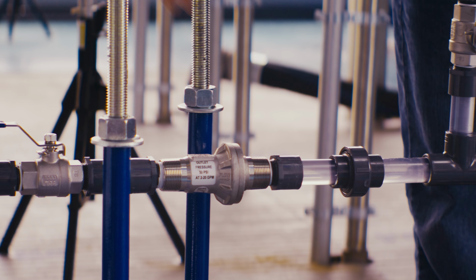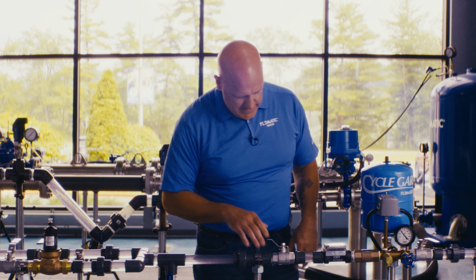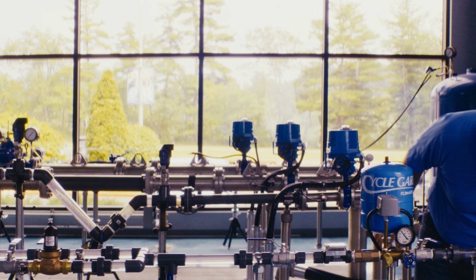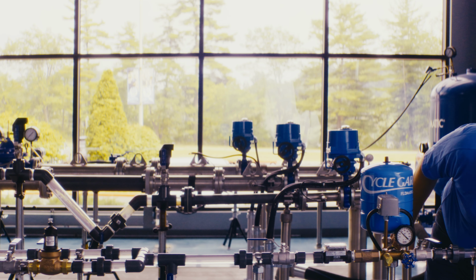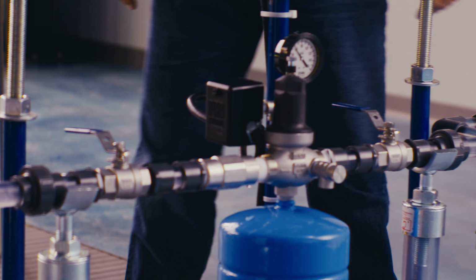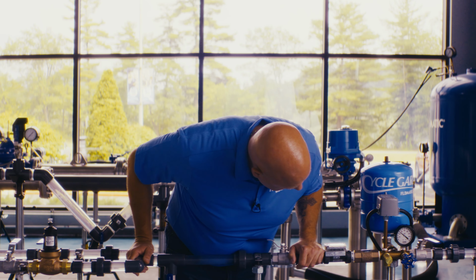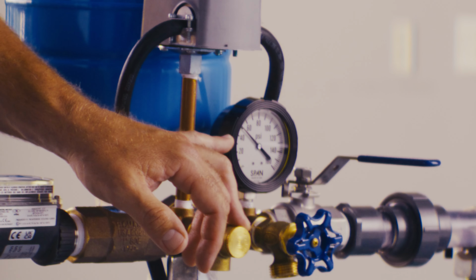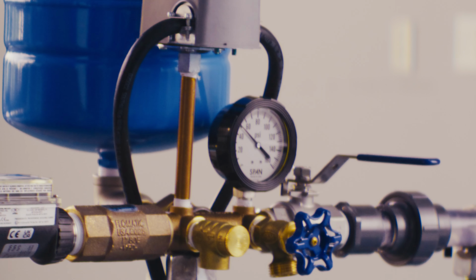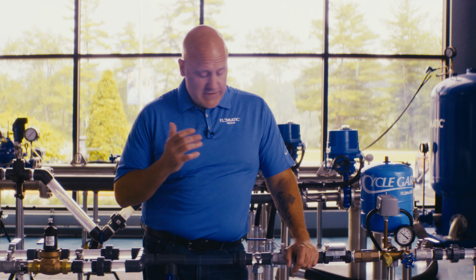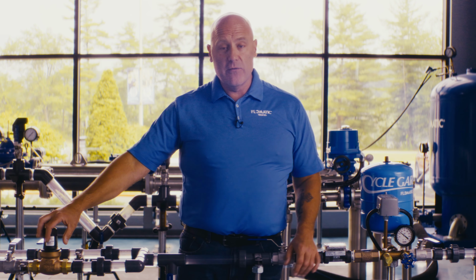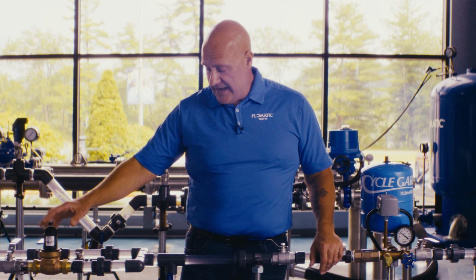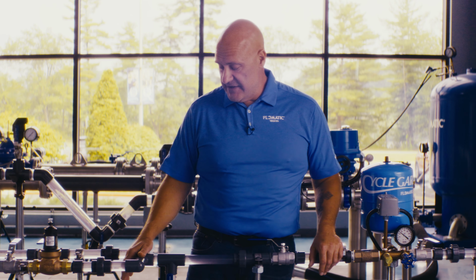So let me make sure I have the correct valves open. I do, and we will run it again. So our pump just kicked on, and you'll notice 50 PSI. Okay, so again, the C153 intended for in-the-well service with an in-the-well tank, non-adjustable, is going to perform the same as the other ones that we're showing you. However, we cannot make adjustments. So this has to be ordered from the factory with the desired pressure of your system.